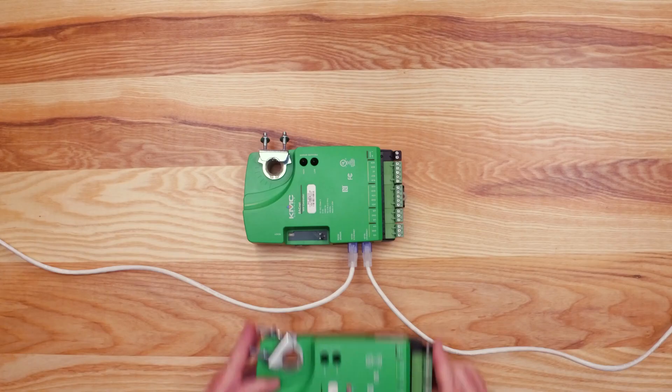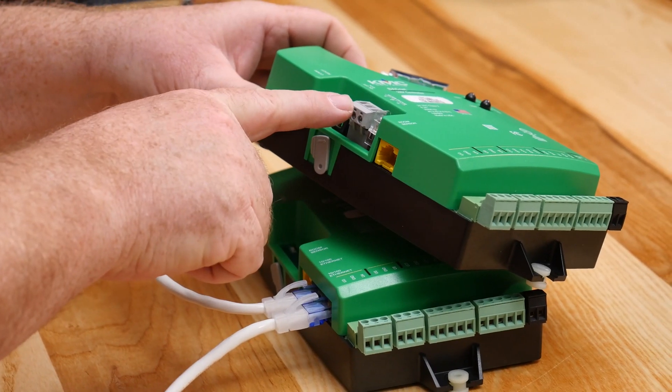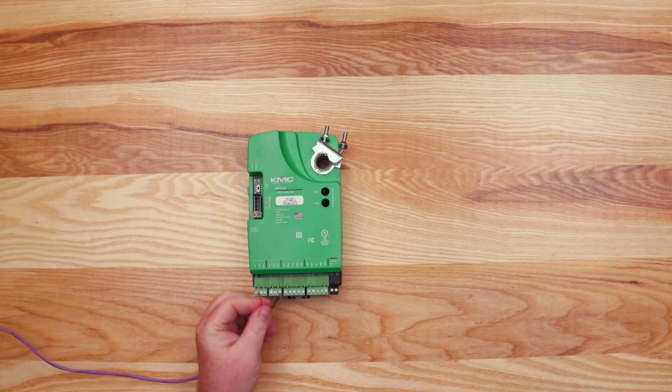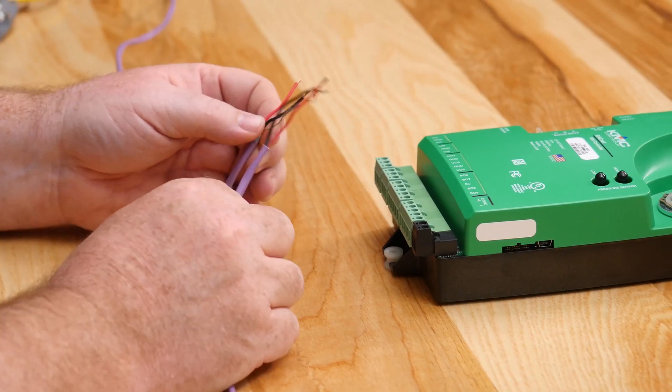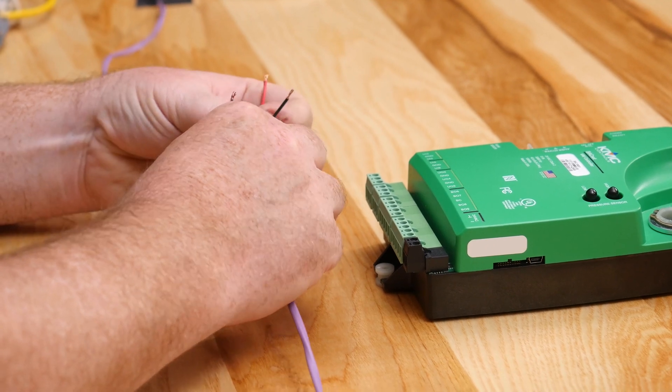We also offer a BACnet over MSTP version, where the two Ethernet ports are replaced with an MSTP terminal block. When wiring to a BACnet over MSTP network, you will have three wires. Make sure to use 18-gauge twisted shielded cable for your network.